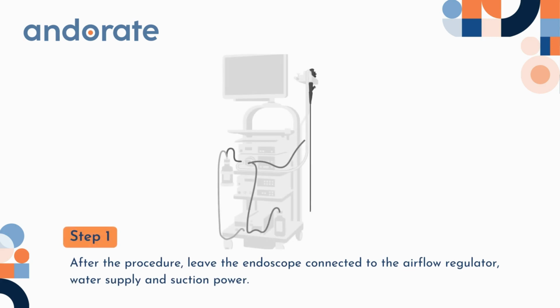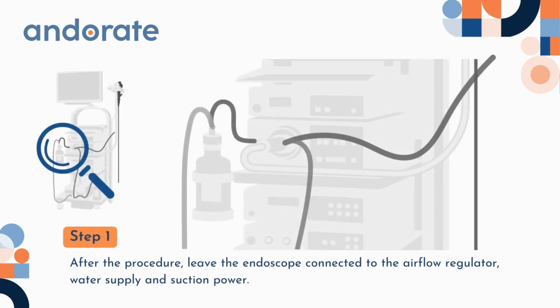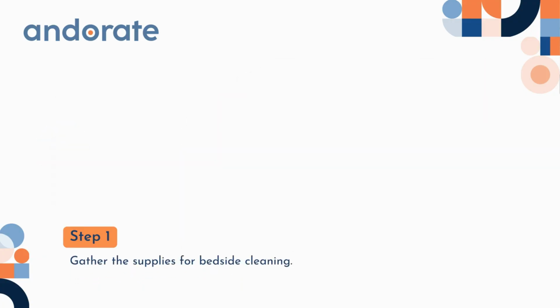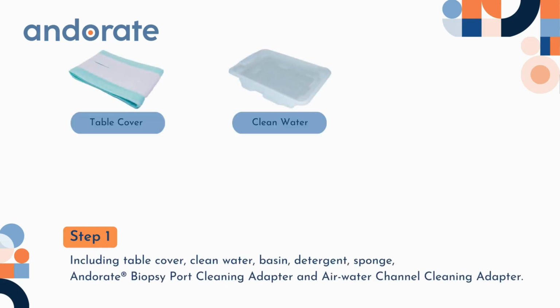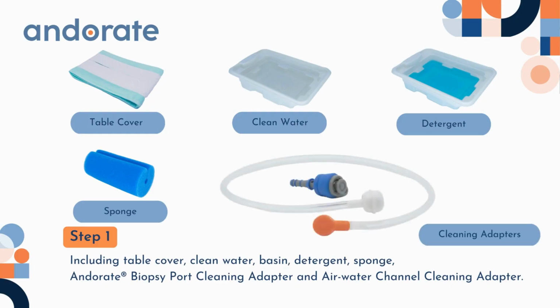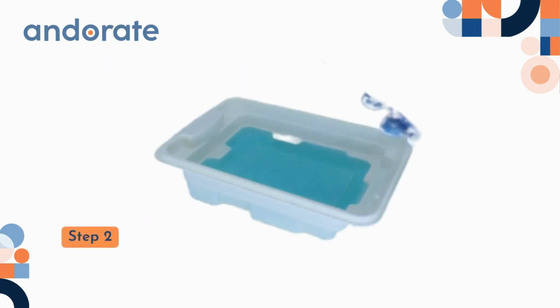Step 1. After the procedure, leave the endoscope connected to the airflow regulator, water supply, and suction power. Gather the supplies for bedside cleaning, including table cover, clean water, basin, detergent, sponge, Andorate biopsy port cleaning adapter, and air-water channel cleaning adapter.